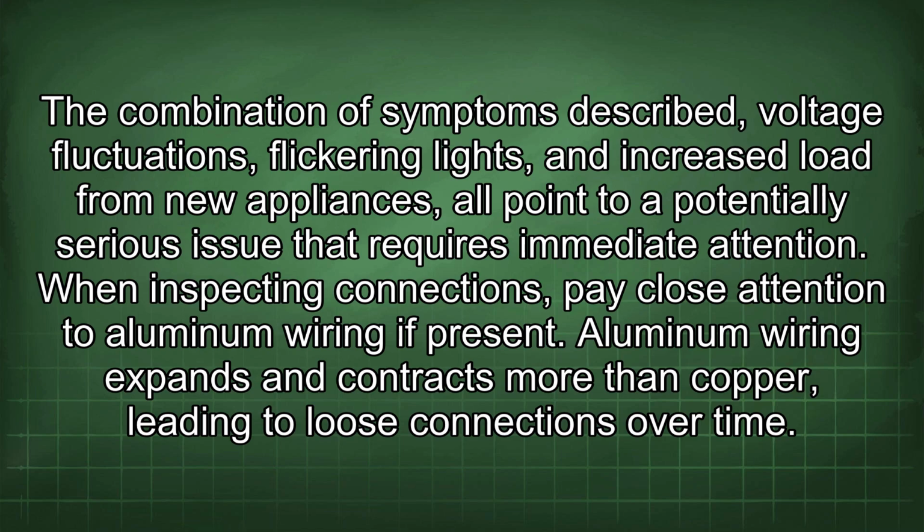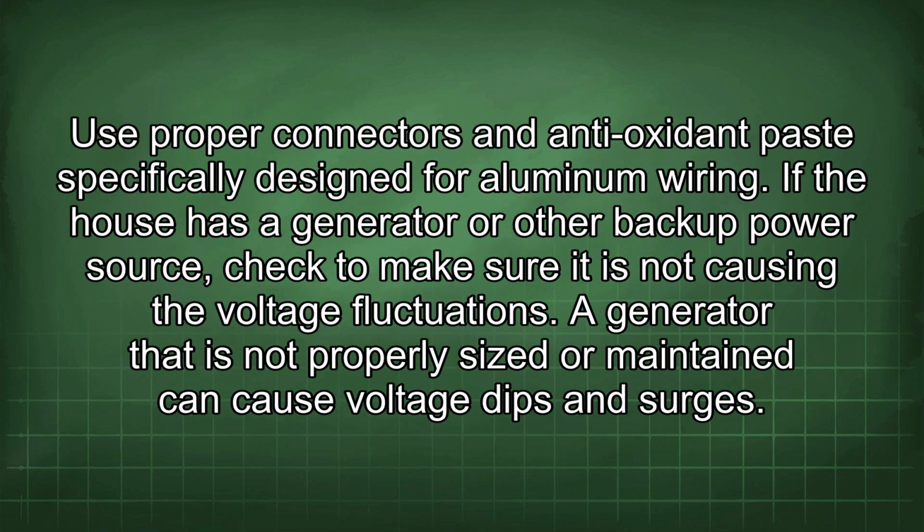When inspecting connections, pay close attention to aluminum wiring if present. Aluminum wiring expands and contracts more than copper, leading to loose connections over time. Use proper connectors and antioxidant paste specifically designed for aluminum wiring.